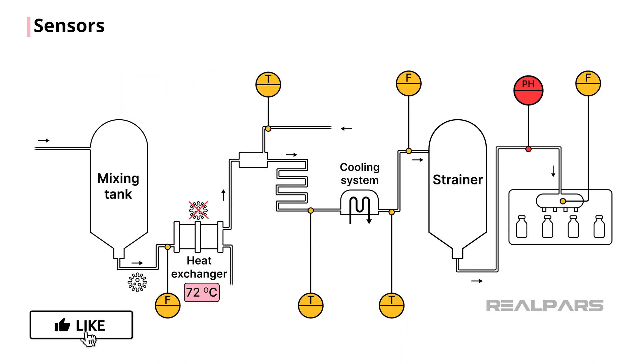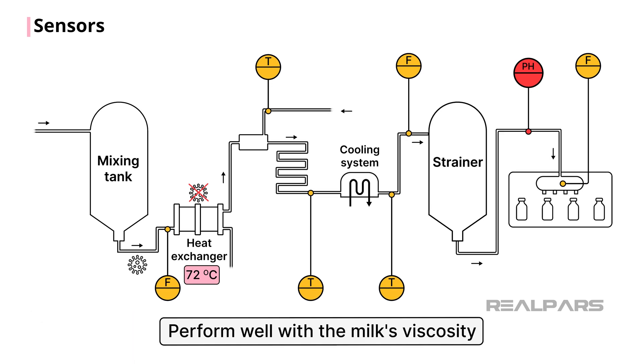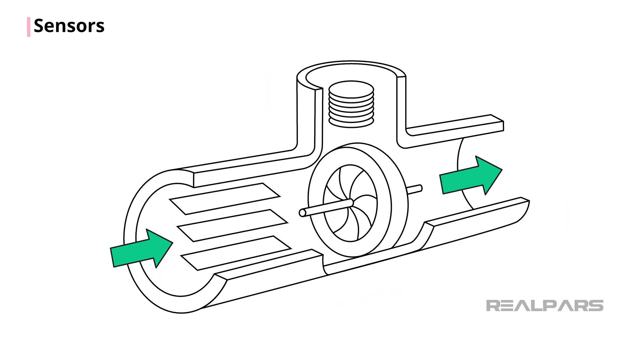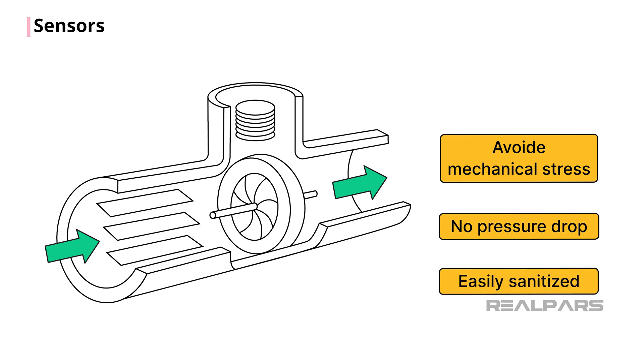To measure flow rates, turbine or electromagnetic flow meters are used, since they are able to perform well considering the viscous nature of the milk. Because these flow meters do not cause large restrictions in the pipe, they do not cause undue mechanical stresses on the structure of the milk fats and proteins. Turbine and electromagnetic flow meters have virtually no pressure drop and are easily sanitized.